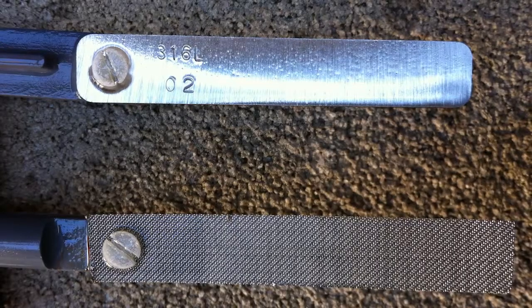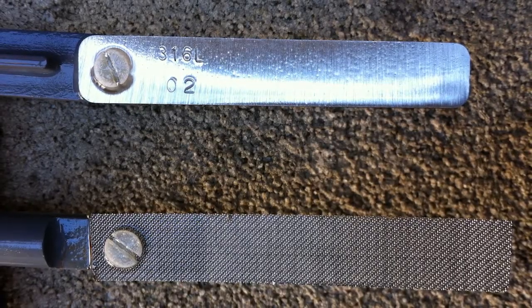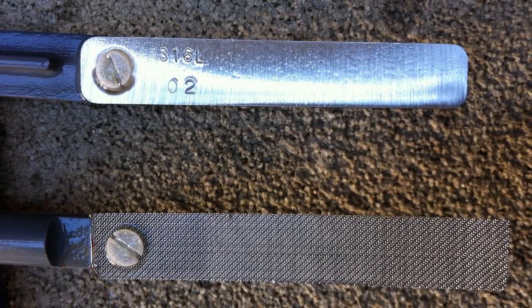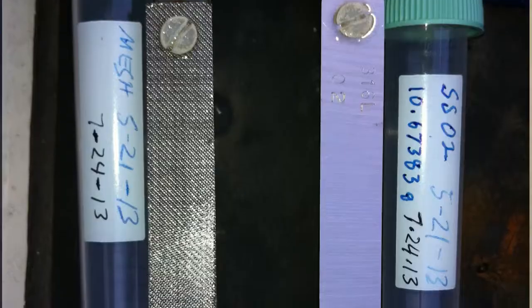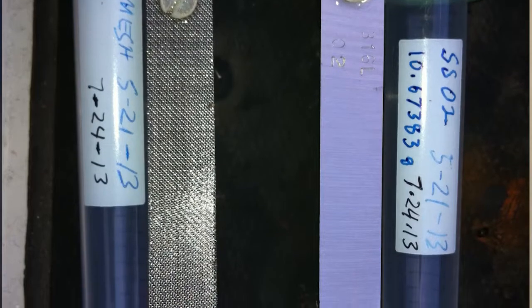For the sessile organisms, we use two types of corrosion coupons suspended in the cooling tower water to determine if sessile microorganisms, the ones that stick to surfaces, adhere to the coupon.